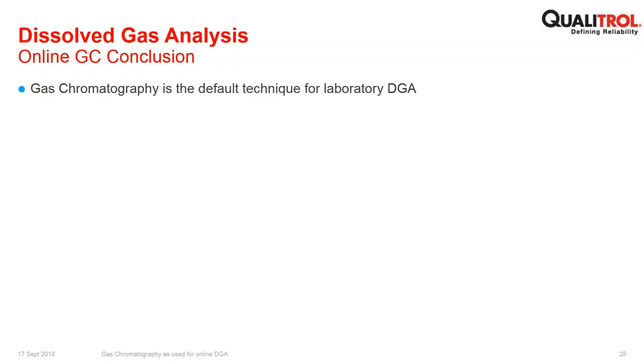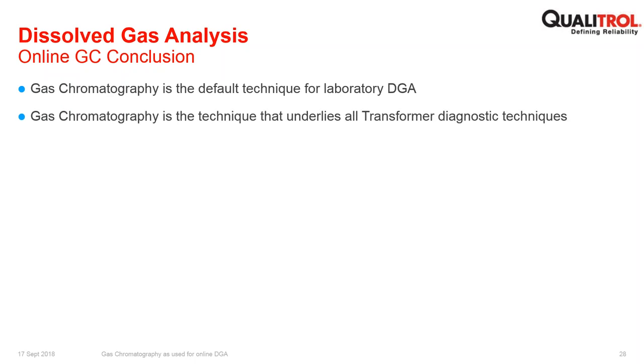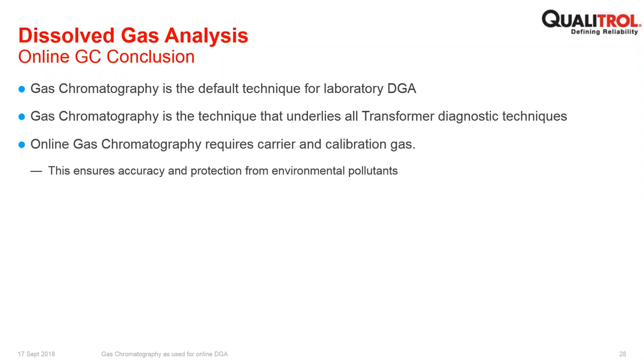And finally, the conclusion. Gas chromatography is the default technique for laboratory DGA. It's the technique that underlies all transformer diagnostic techniques. What I'm saying here is that they're all based on data collected from laboratory gas chromatography systems, and therefore the alignment will be much better. Online gas chromatography requires carrier and calibration gas, and this ensures accuracy and protection from environmental pollutants. And of course, carrier gas can be provided in a cylinder that will give carrier gas for the lifetime of the product.